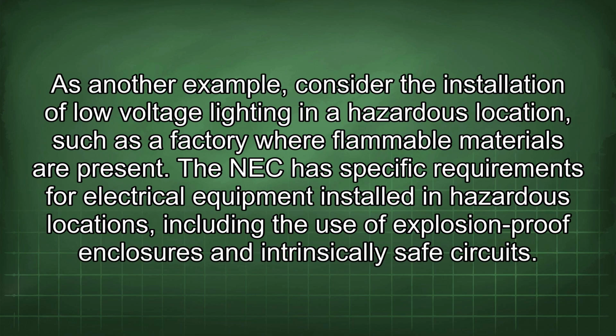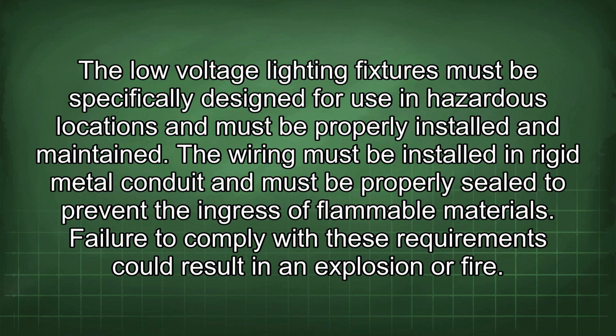As another example, consider the installation of low-voltage lighting in a hazardous location, such as a factory where flammable materials are present. The NEC has specific requirements for electrical equipment installed in hazardous locations, including the use of explosion-proof enclosures and intrinsically safe circuits. The low-voltage lighting fixtures must be specifically designed for use in hazardous locations and must be properly installed and maintained. The wiring must be installed in rigid metal conduit and must be properly sealed to prevent the ingress of flammable materials. Failure to comply with these requirements could result in an explosion or fire.